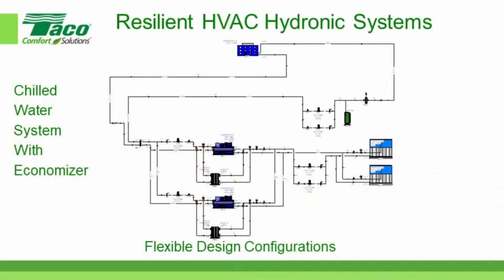Another configuration is a chilled water system. This is a central chilled water system using what's affectionately known as an economizer. Let's do summertime first: we run typical chillers, which generate chilled water for distribution to a building, and ultimately reject their heat to the cooling tower.